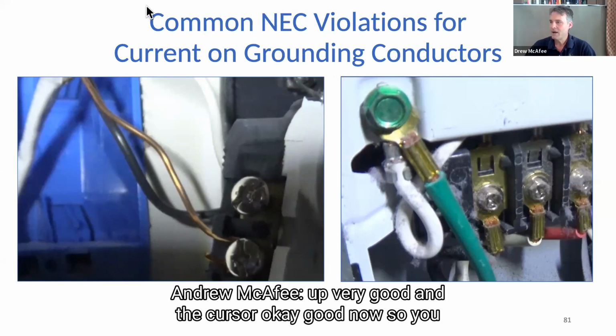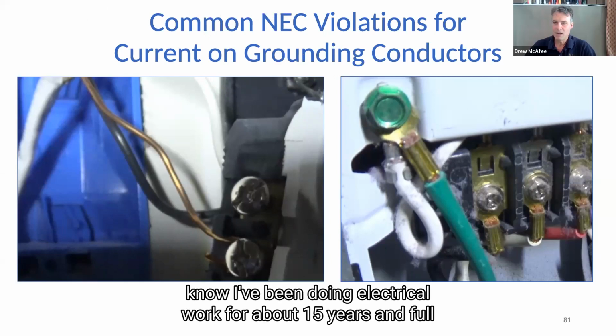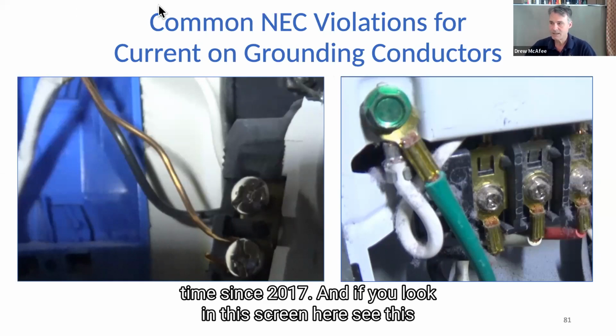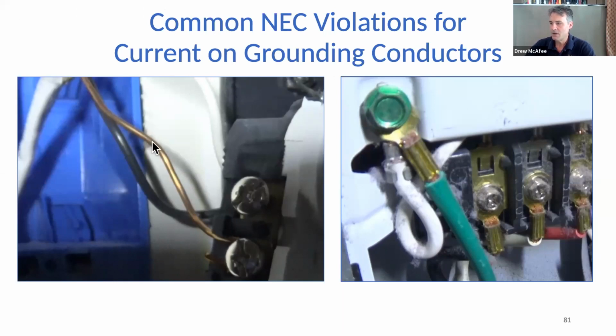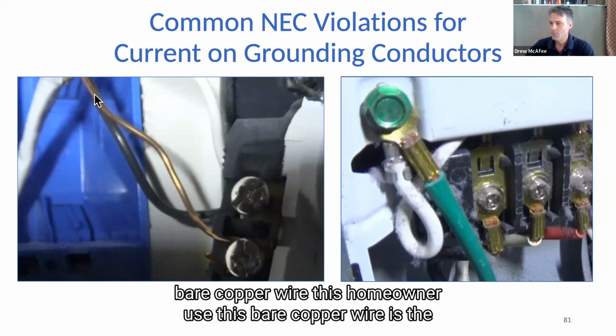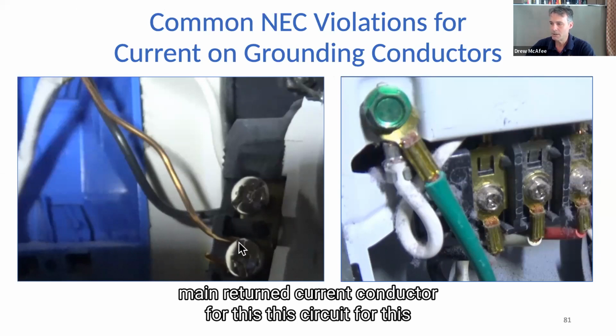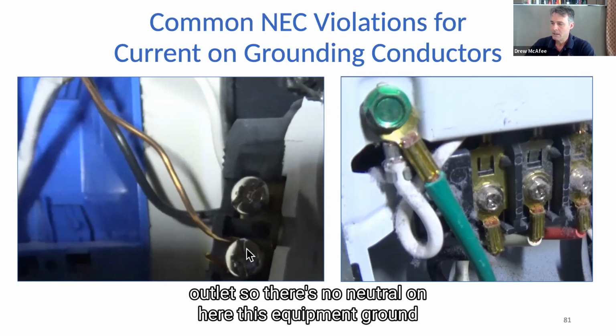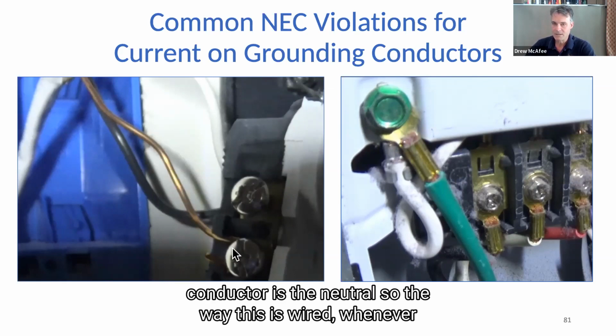Okay, good. Yep. Now, I've been doing electrical work for about 15 years and full-time since 2017. If you look at this screen, see this bare copper wire. This homeowner used this bare copper wire as the main return current conductor for this outlet circuit. So there's no neutral on here. This equipment ground conductor is the neutral.